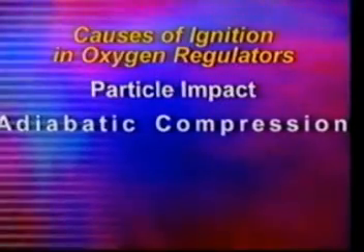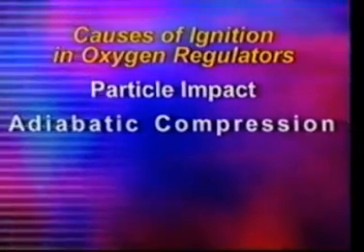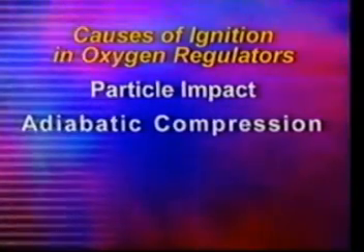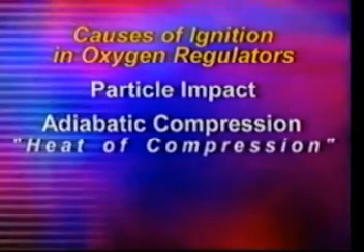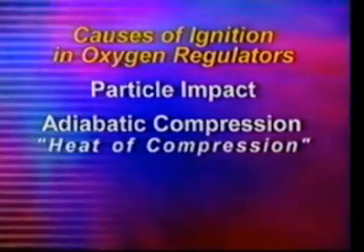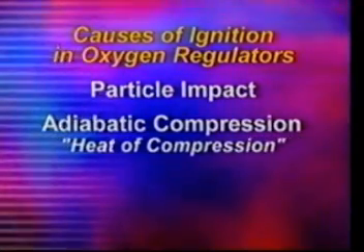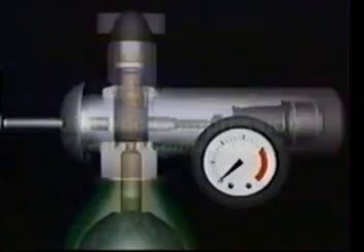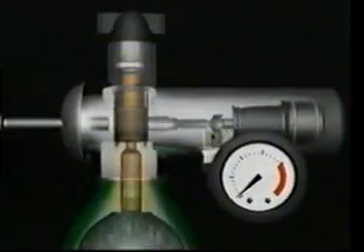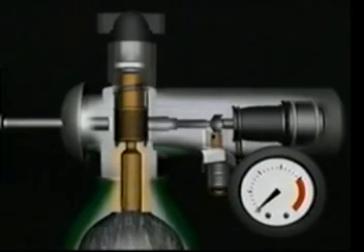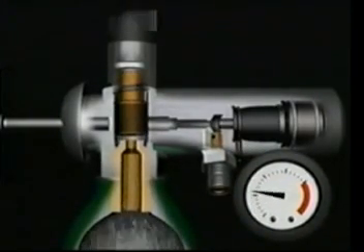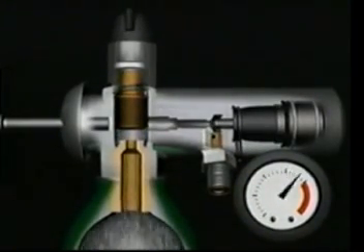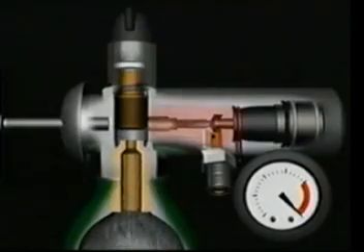Another contributing factor is adiabatic compression, also called the heat of compression. This happens when you open the post valve and pressurize the regulator. Oxygen rushes into the high pressure side of the regulator.